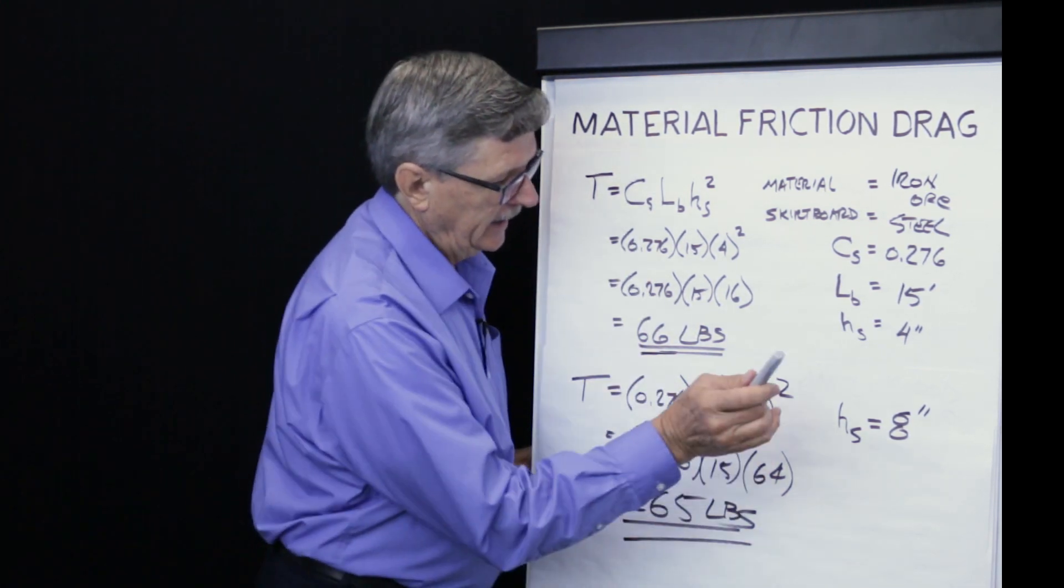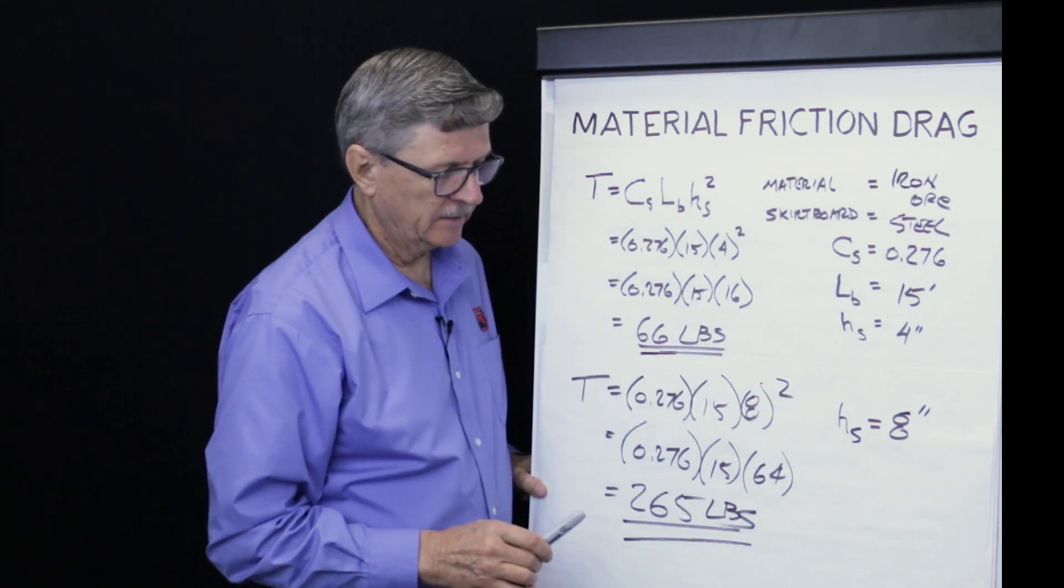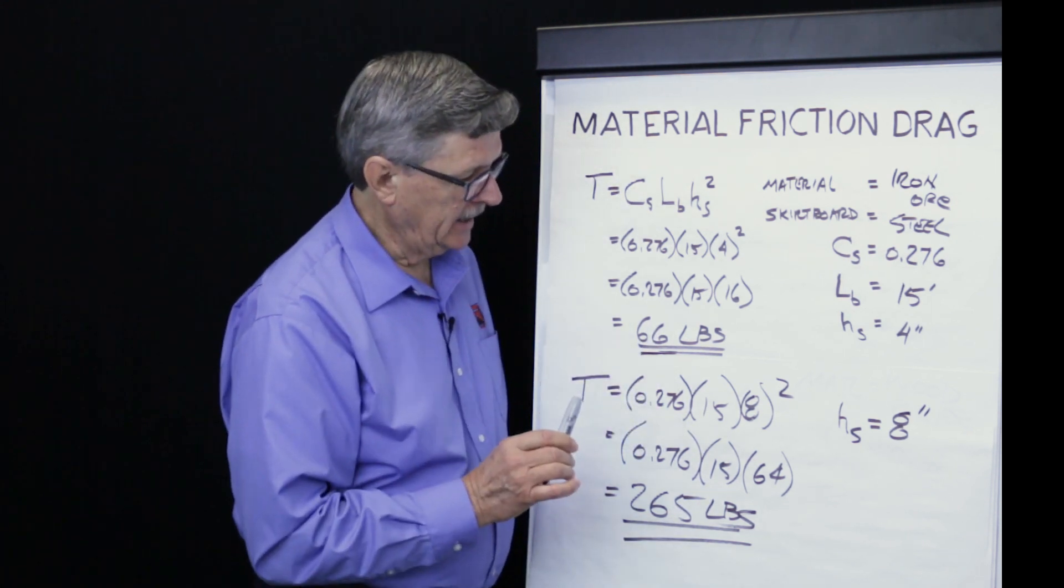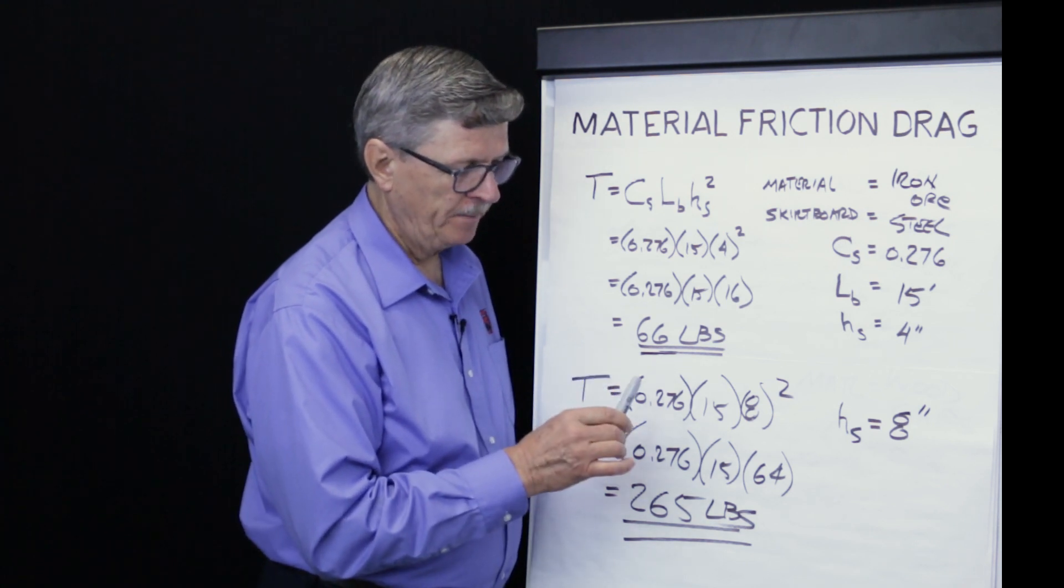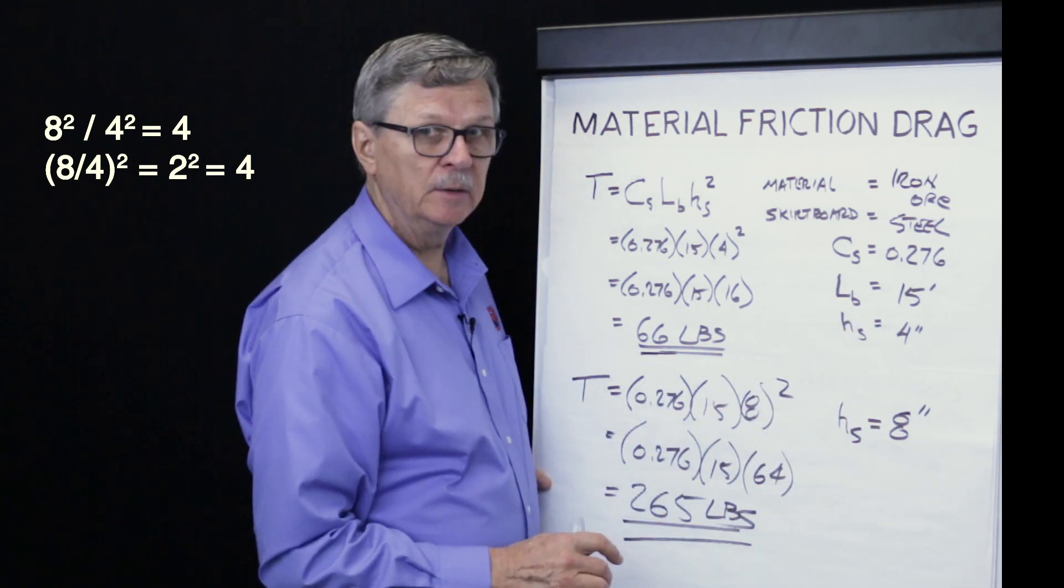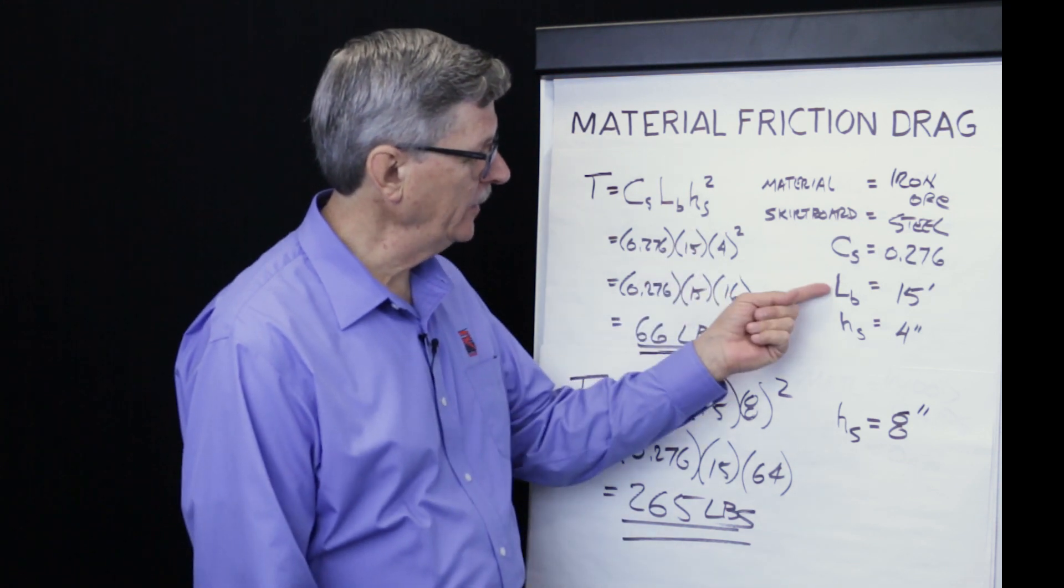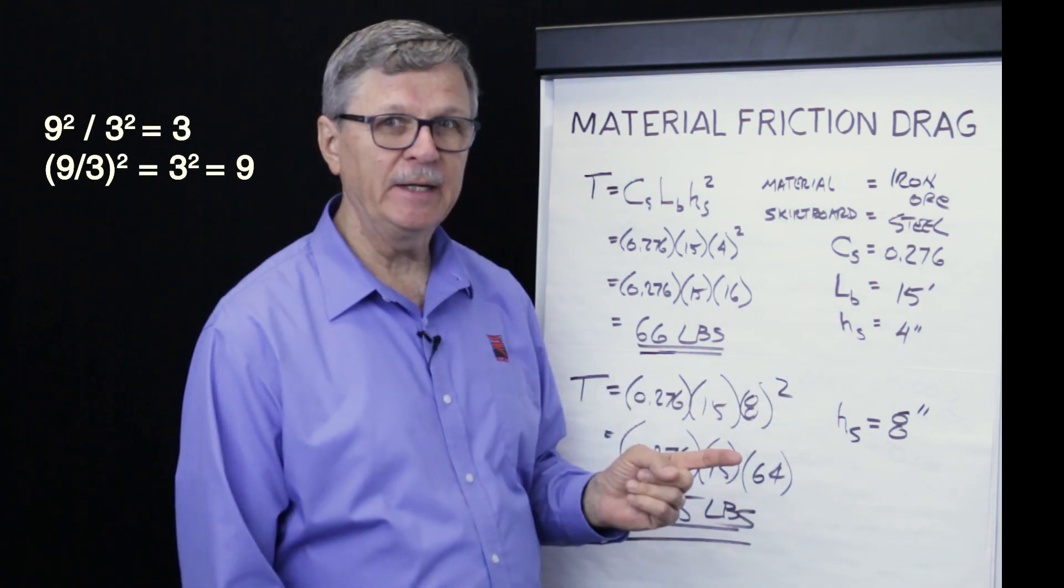Notice that when the iron ore has a depth of 8 inches instead of 4 inches in the zone, the frictional drag from the material equals 265 pounds instead of 66 pounds. That's because the result is proportional to the square of the ratio of the depths. In other words, 8 divided by 4 equals 2, 2 squared is 4. Therefore, this result is 4 times this result. If we were to compare the results of a 3 inch depth of material versus a 9 inch depth of material, notice that 9 divided by 3 is 3, 3 squared is 9. That would give us a frictional drag here 9 times larger than here.